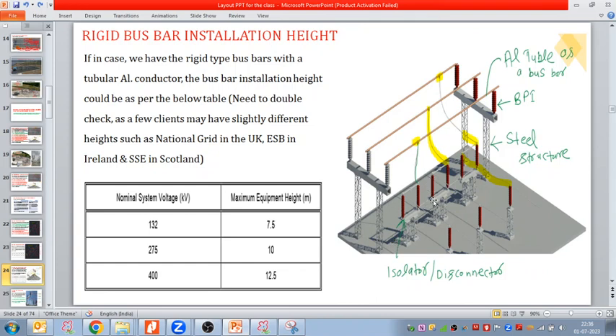Am I clear? Yes sir. Plus a certain height from the ground, plus between the bus bar and the equipment we have to maintain the minimum phase-to-phase clearances. So equipment height plus phase-to-phase clearances - after that we can plan the main bus bar height. Due to that reason this height of the bus bar comes slightly more from the ground, because it's equipment plus phase-to-phase clearances, which we will discuss as well.